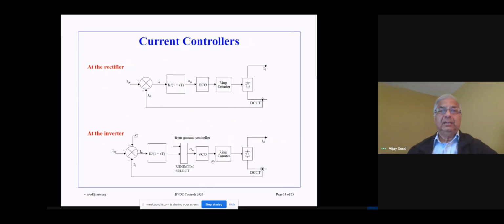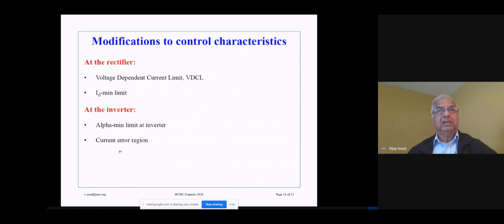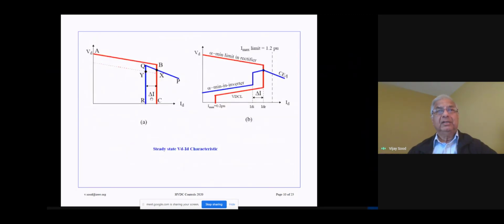Now, at the inverter, we have a similar control system. So we have a measurement of the DC current. That is taken and compared with the ordered value of the rectifier current order. So you can see that these two are the same. We have to subtract the current margin from this value. Remember, we were talking about this current margin over here. So the rectifier current order is set at this value, minus the margin gives you the current order at the inverter.